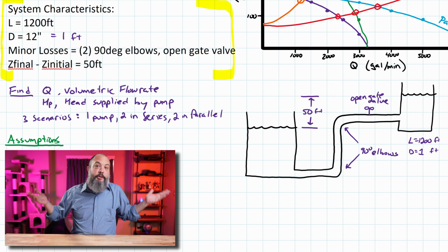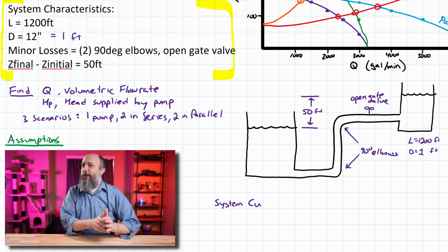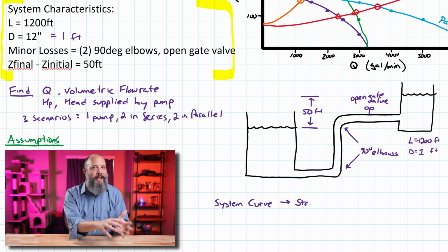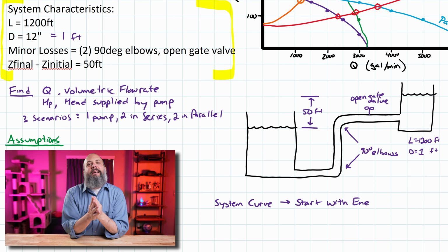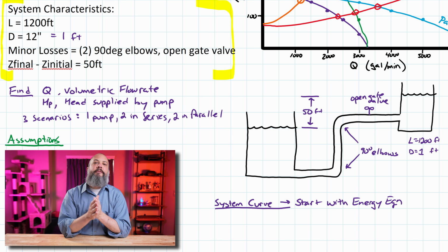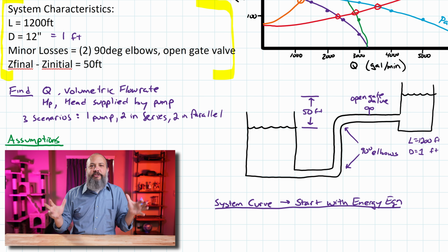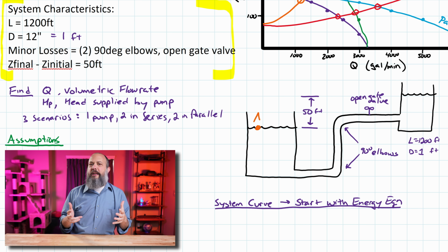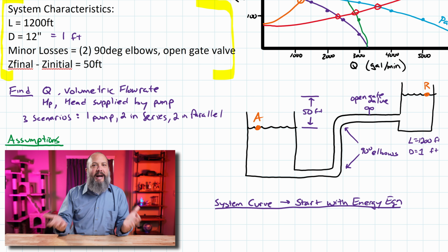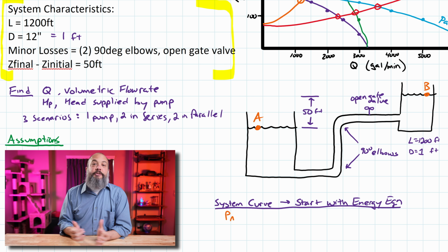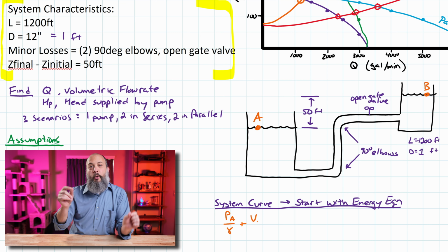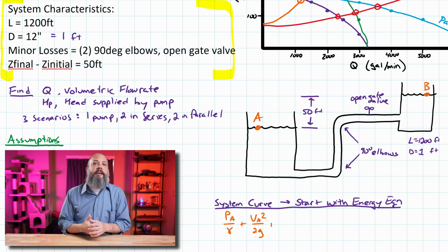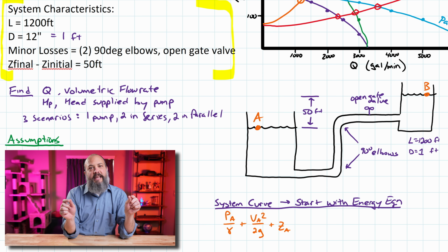And of course, once you make a drawing, then you write down some equations. That's the whole point of making a drawing, is to make your equations from the drawing. So a system curve starts off with the energy equation, right? This falls under the category, if you're looking up in a textbook, of probably conduit flow or flow through pipes. And so that's the energy equation. So I need to find 2 points along a Bernoulli flow line. So I'm going to choose point A and point B from the top of each tank. And if you have a tank, the top of the tanks is always a great place to choose for points, because a ton of terms in your equation are going to cancel out.